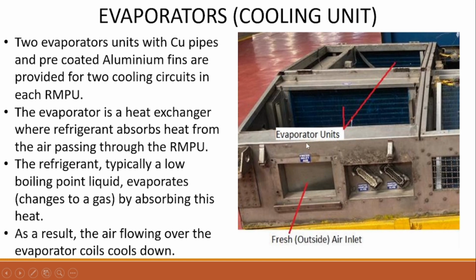Coming to the evaporators, two evaporator units with CU pipes and pre-coated aluminum fins are provided for the two cooling circuits in each RMPU. The evaporator is a heat exchanger where refrigerant absorbs heat from the air passing through the RMPU. The refrigerant, typically a low boiling point liquid, evaporates by absorbing this heat. As a result, the air flowing over the evaporator coils cools down.